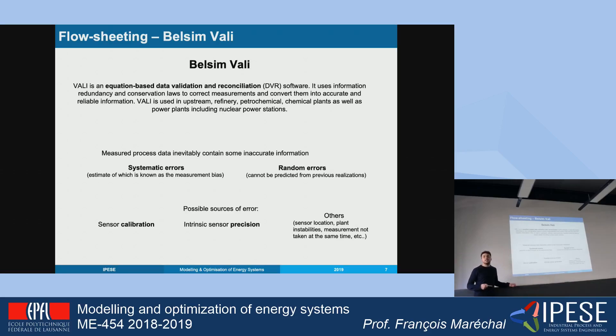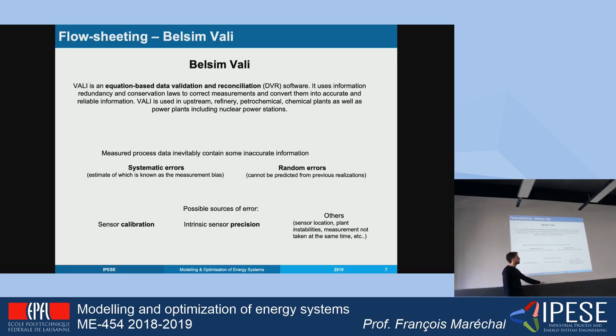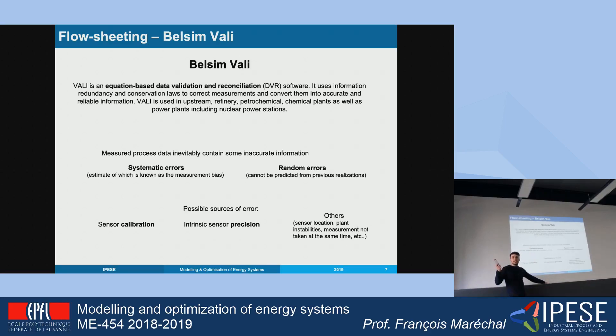Vali is a really good tool because every sensor installed in any industrial plant is affected by two different kinds of errors: systematic errors and random errors. Systematic errors are normally due to calibration and estimate the measurement bias. Random errors are not correlated to previous samples — they are truly random and connected to the intrinsic sensor precision. There are also other factors that can impact measurement quality, such as the location of the plant, availability, and shutdowns.